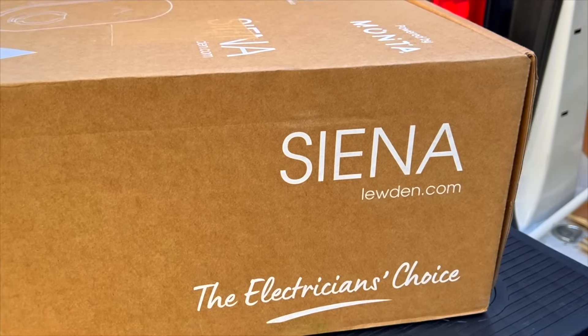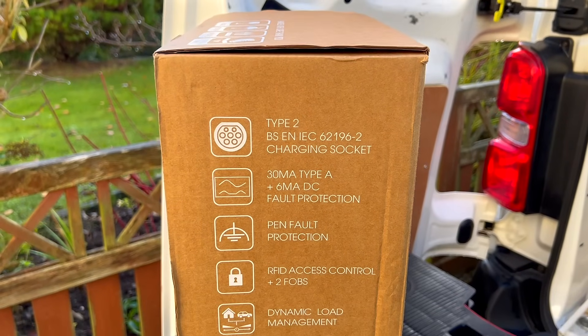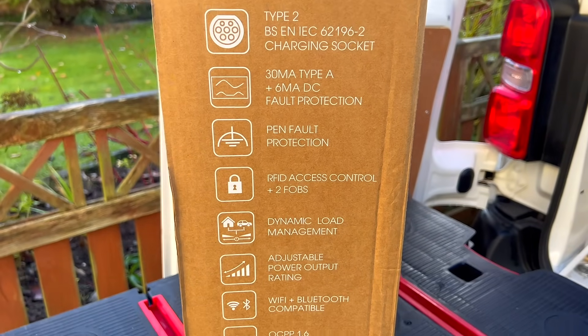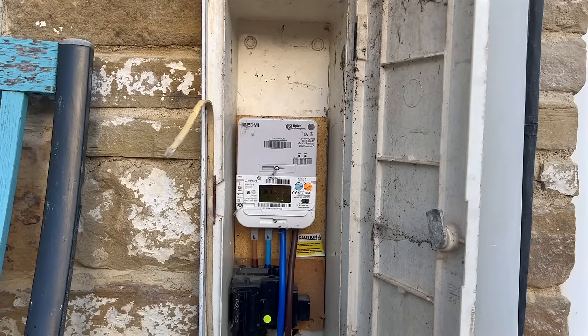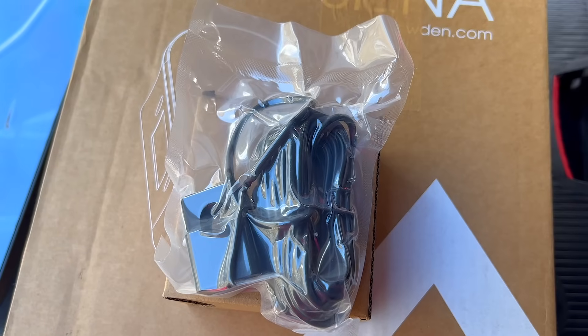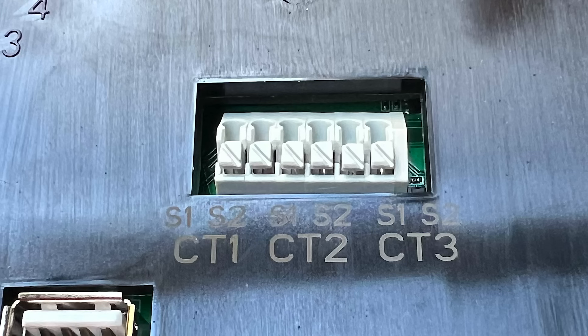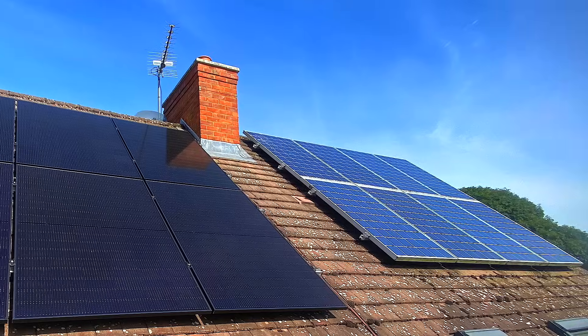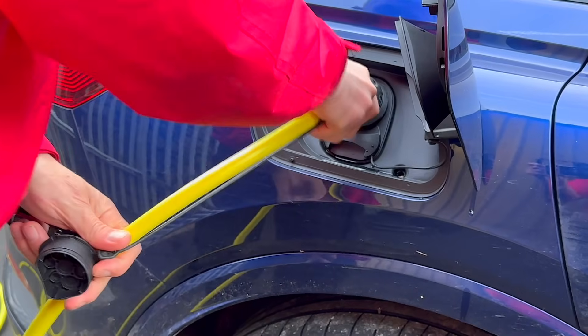Joining the EV space a little later than others gives you time to reflect on what the market really needs. Lewden have decided to throw the kitchen sink at the problem and included everything. If you need load balancing because you have a 60 amp supply, a current transformer is included. You can also add an additional CT to make the charger compatible with solar PV installations, allowing EV charging from excess solar energy.